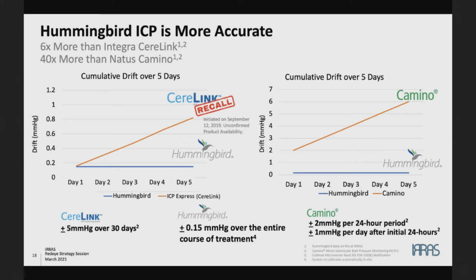If you look at the instructions for use of Hummingbird compared to the market leaders, CereLink, sold by Integra, and Camino, sold by Natus, there is a significant difference in long-term accuracy of the pressure reading. Hummingbird recalibrates its reading every hour, so the phenomenon of drift, which is error stacking up over a period of time, does not occur.